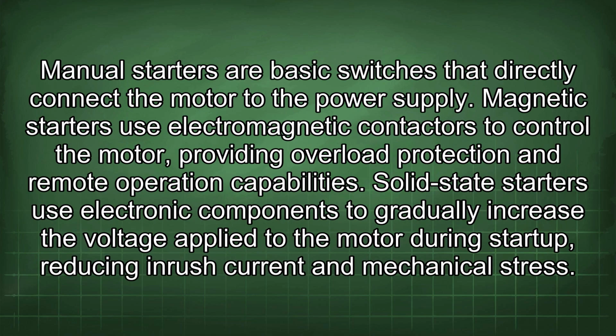Manual starters are basic switches that directly connect the motor to the power supply. Magnetic starters use electromagnetic contactors to control the motor, providing overload protection and remote operation capabilities. Solid-state starters use electronic components to gradually increase the voltage applied to the motor during startup, reducing inrush current and mechanical stress.